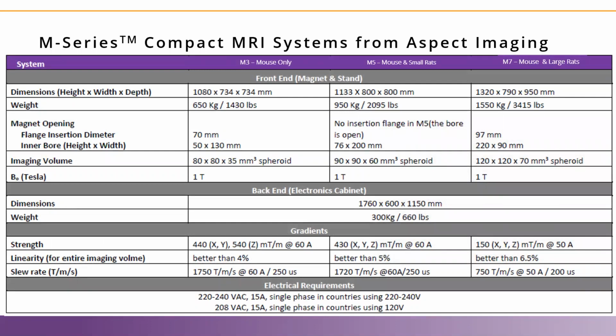There's 3 different systems, the M3, the M5, and the M7. The only difference between those systems is the magnet itself and the size of that magnet. And the difference really comes into the size of the bore or the opening of the magnet. So the M3 is a mouse-only system, and that's the system that I used during the demonstration last week. The M5 has a slightly larger opening and allows us to acquire images from mice and small rats. And the M7 is a much larger opening, giving us mice and large rats up to about 600 grams.